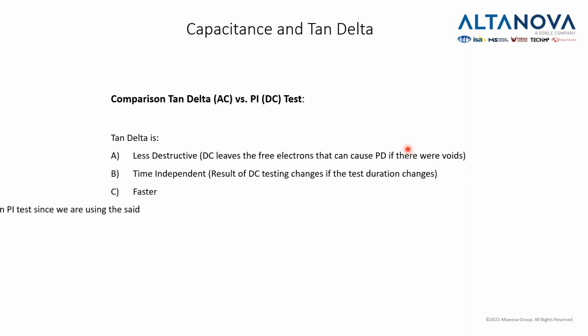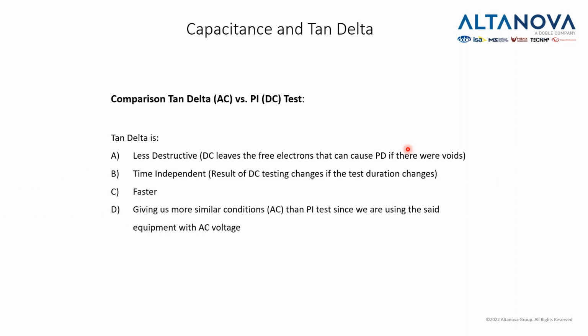We'll skip this, or let me say that the difference between AC and DC test is that the AC test is less destructive. So tan delta is less destructive in respect to the so-called polarization index test. It is also time independent because you can get repeatable results with an AC test, with DC not often. It is a faster test and it gives more similar conditions because we are using an AC voltage, which is normally used on our transformers. The DC voltage is not used on transformers.